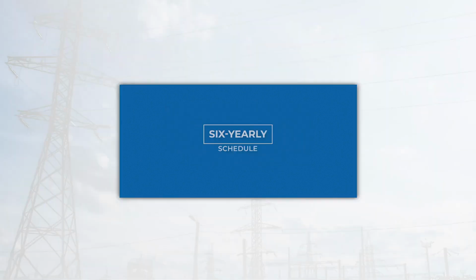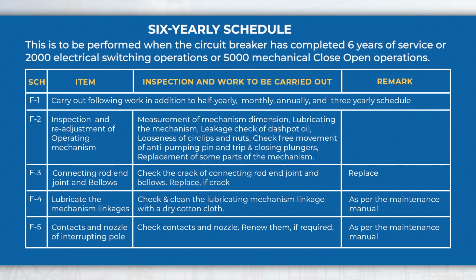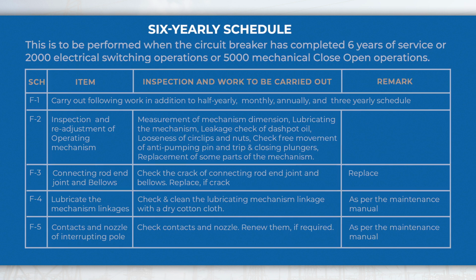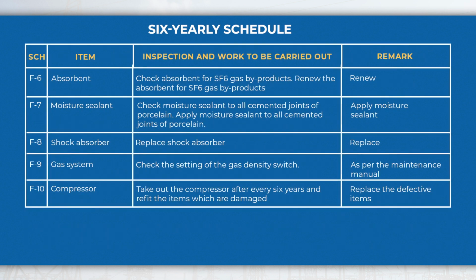6-yearly schedule. This is to be performed when the circuit breaker has completed 6 years of service or 2000 electrical switching operations or 5000 mechanical close-open operations. In 6-yearly schedule, perform the activities like checking and readjustment of operating mechanism, lubricating the mechanical linkage, checking of moisture sealant, gas system setting, compressor, etc. in addition to 3-yearly schedule, annually, half-yearly, and monthly schedule activities.